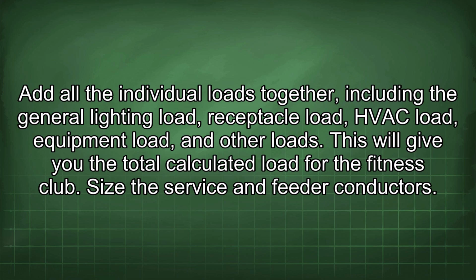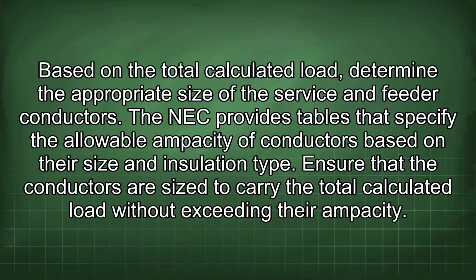Size the service and feeder conductors. Based on the total calculated load, determine the appropriate size of the service and feeder conductors. The NEC provides tables that specify the allowable ampacity of conductors based on their size and insulation type. Ensure that the conductors are sized to carry the total calculated load without exceeding their ampacity.